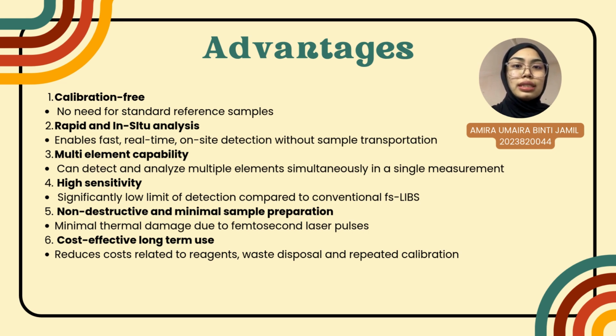Another major strength is its multi-element capability. With just a single measurement, we can detect and quantify multiple elements at once, saving both time and effort. Next, the technique also offers high sensitivity with significantly lower detection limits compared to traditional FSLIBS methods. This makes it suitable even for trace level analysis. Since it uses femtosecond laser pulses, the method is non-destructive and requires minimal sample preparation while also reducing thermal damage to the sample surface. Lastly, it is cost-effective in the long run. By eliminating the need for reagents, standard calibrations, and frequent maintenance, it helps cut down on operational costs and minimize waste.